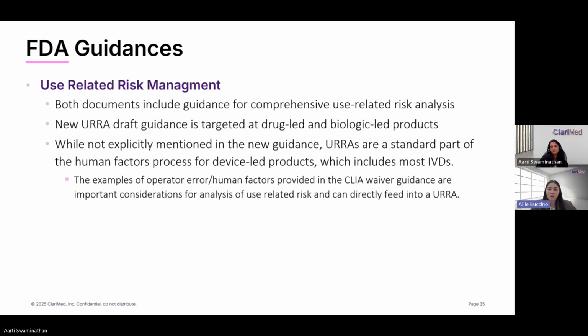The URRA is something that's been used in human factors for device-led products; it's standard practice. While the CLIA waiver doesn't mention URRA specifically, it is a good tool for doing a comprehensive use-related risk analysis. The CLIA waiver guidance points out different operator errors and human factors that could lead to use error for consideration, and those feed into the URRA.